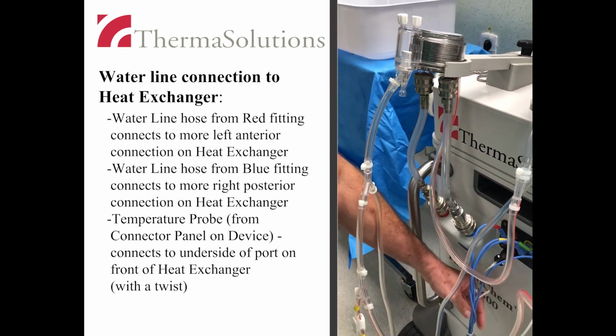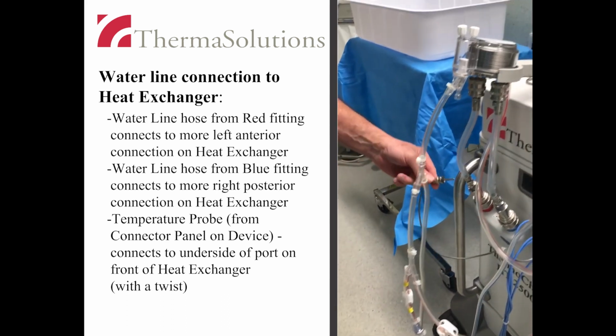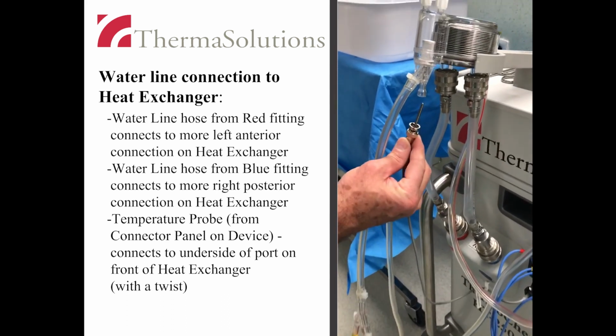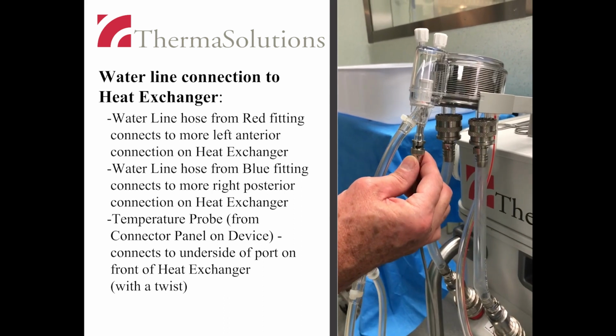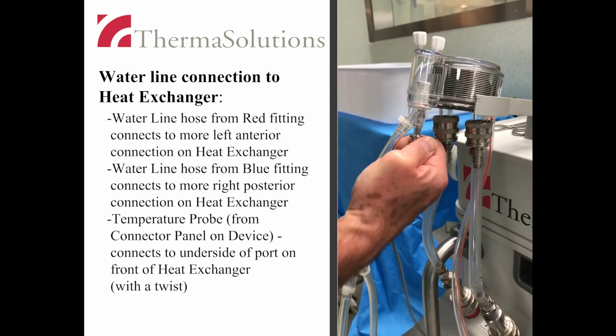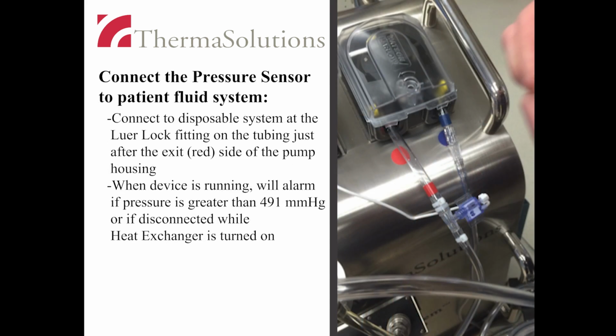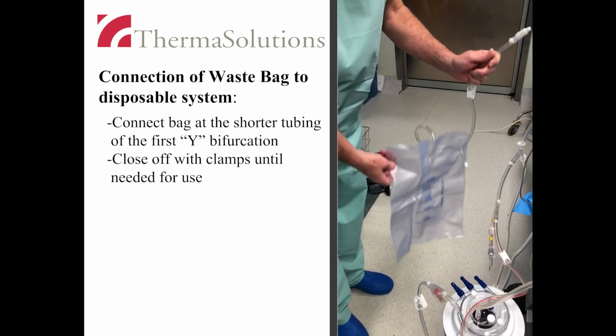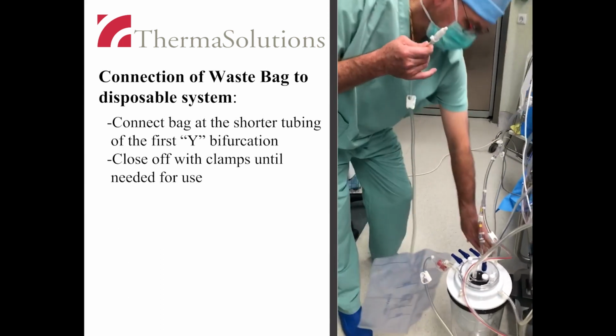The gray temperature probe from the connector panel on the device connects to the anterior port of the front of the underside of the heat exchanger. Insert the pin on the probe and twist to secure. Connect the pressure sensor to the disposable tubing system. The connection point is at the luer lock fitting located on the tubing on the exit side of the pump. This is the left side of the pump with the red dot. Connect the waste bag to the inflow line at the shorter tubing of the first Y bifurcation.